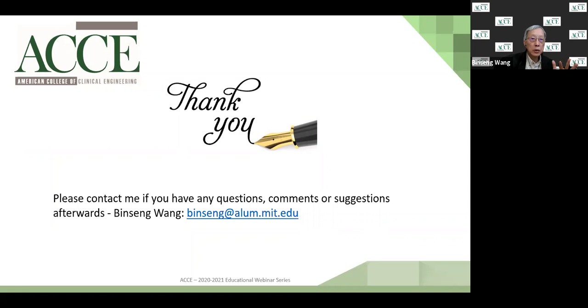Okay, so calibration is actually composed of two parts: calibration verification and calibration adjustment, so-called recalibration. Now, electrical safety test is not mandatory for safety and performance inspection anymore, unless it is a new incoming piece of equipment. Otherwise, routine safety performance inspection in a hospital does not require electrical safety test, at least here in the United States. I cannot say about South Africa, or in this case, Gustavo is from Brazil. No, I cannot say about Brazil. Each country sometimes has its own set of laws, regulations.